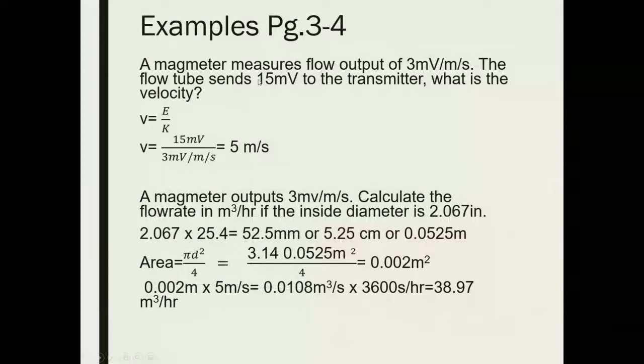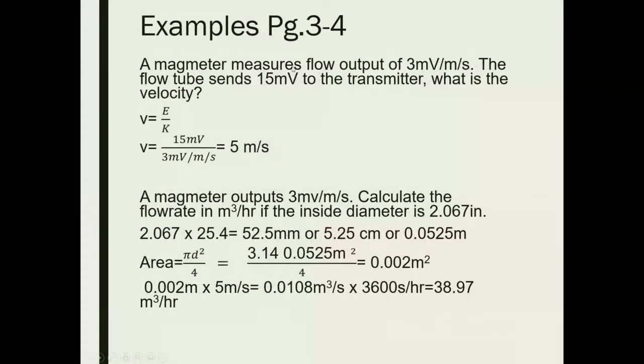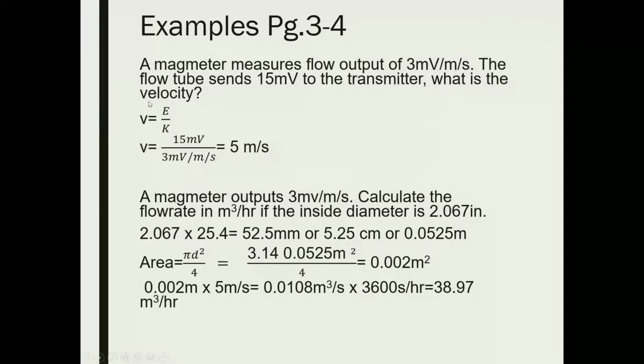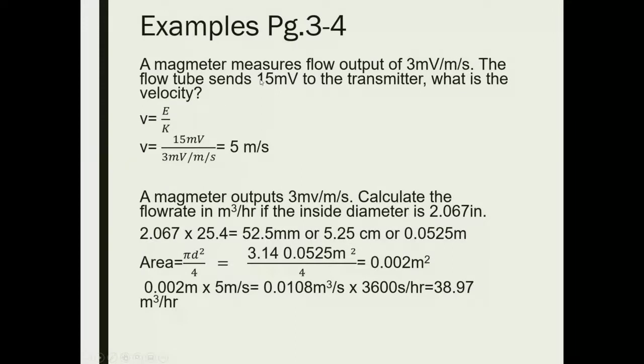Here's a sample problem. A mag meter measures a flow output of 3 millivolts per meter per second. The flow tube sends 15 millivolts to the transmitter. What is the velocity? Taking the formula from the previous slide: velocity equals EMF divided by K factor. So 15 divided by 3 gives us a velocity of 5 meters per second. Nothing too crazy there.